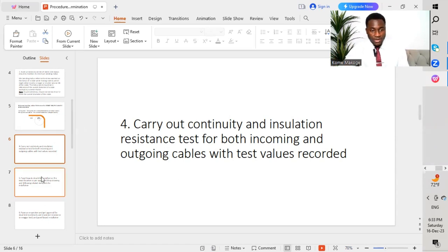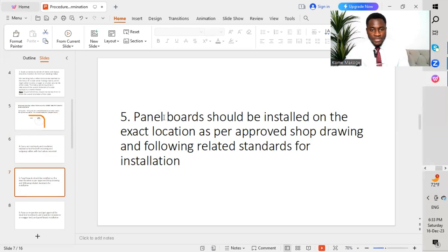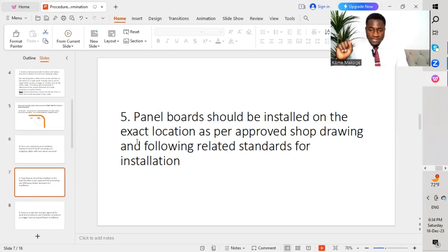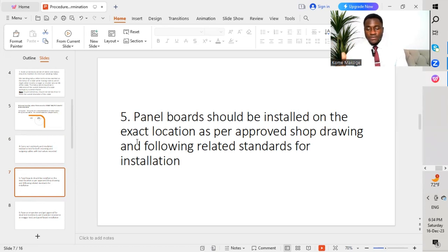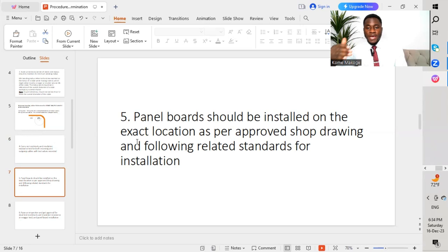The fifth point: the panel board should be installed at the exact location as per the approved shop drawing and following related installation standards. We go through the different shop drawings to carry out the installation of the panel board — whether it is a distribution board, sub main distribution board, MCC (motor control centers), motor control panels, LV panels, or main distribution boards. The installation should match the approved shop drawing as validated by the consultant.